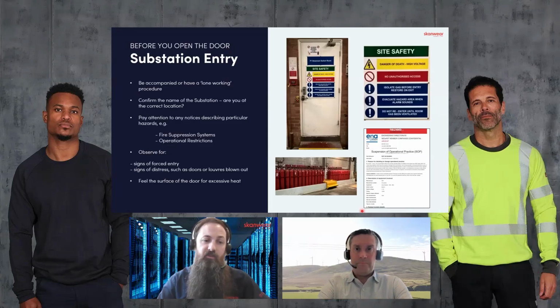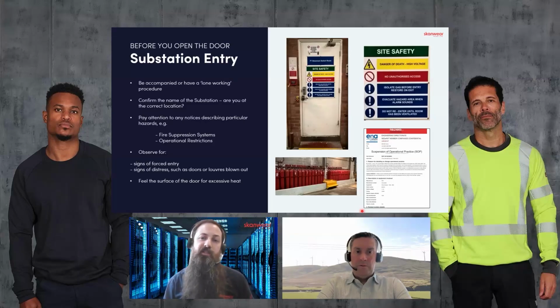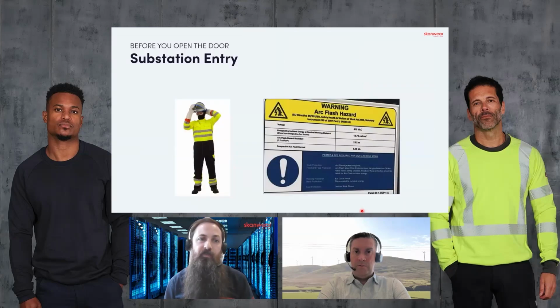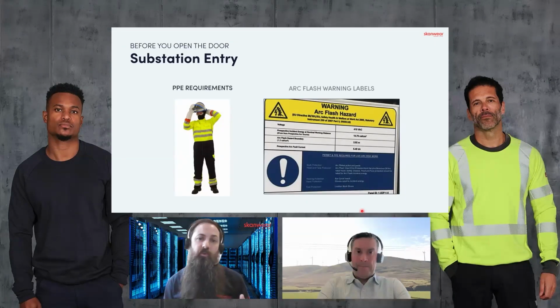Look for signs of forced entry or distress, like louvers or vents blown out, and feel the surface of the door for excessive heat. You'd hope your fire detection system would have given a notification, but some of these sites are in remote locations, so you might not identify there's an issue inside. At the door, hopefully there's been an arc flash survey done, with a label indicating the type of PPE and what it might look like.